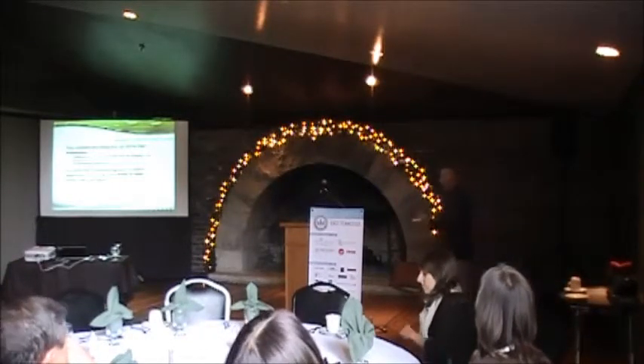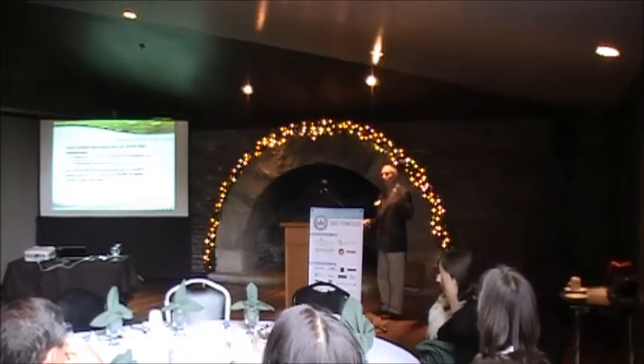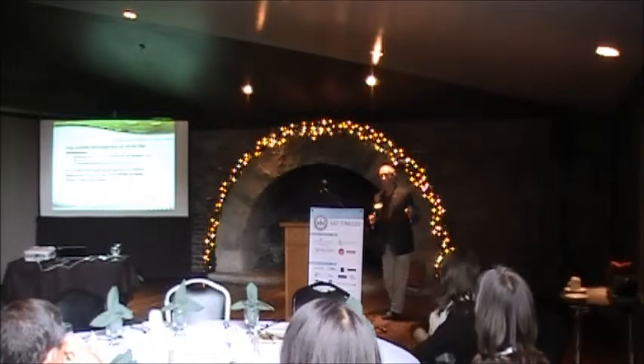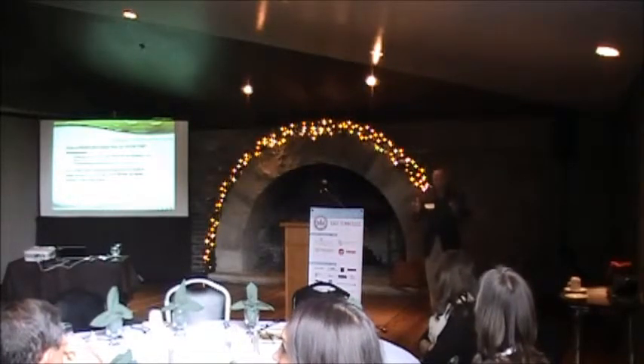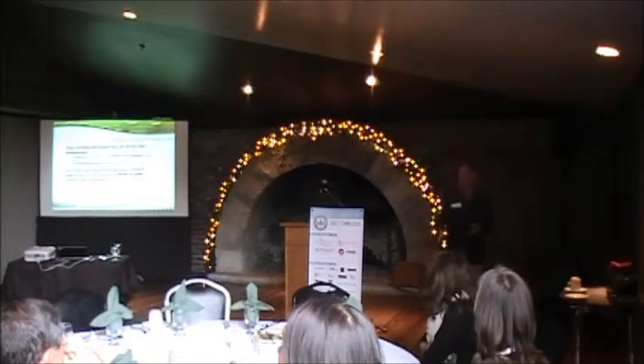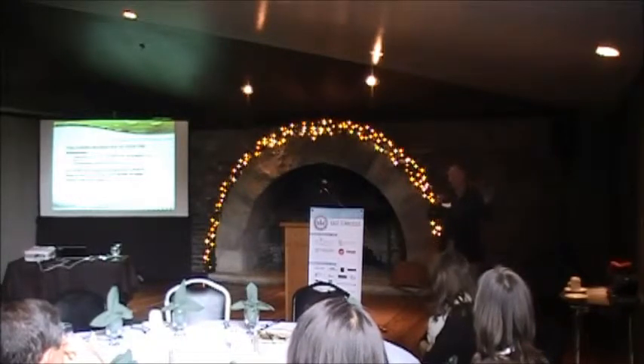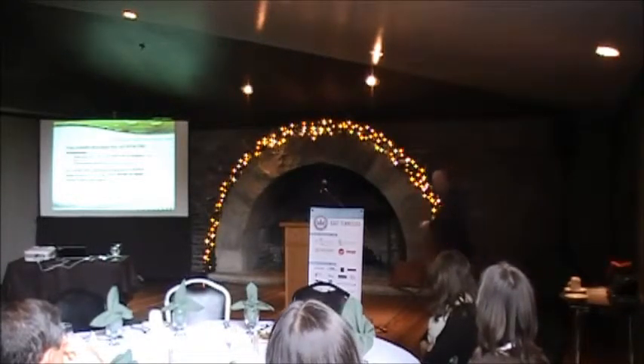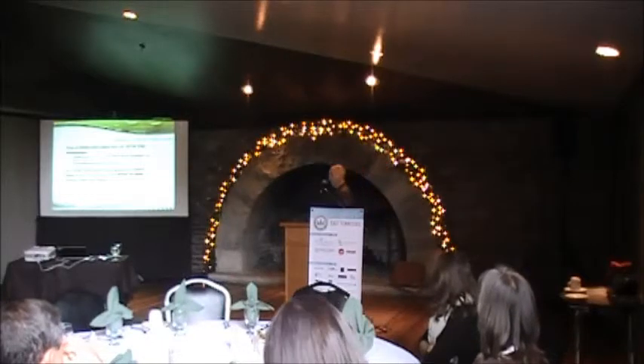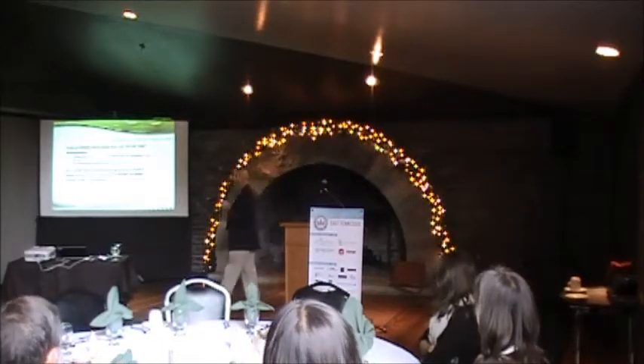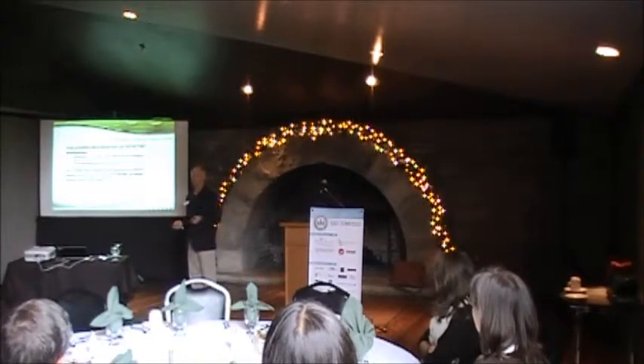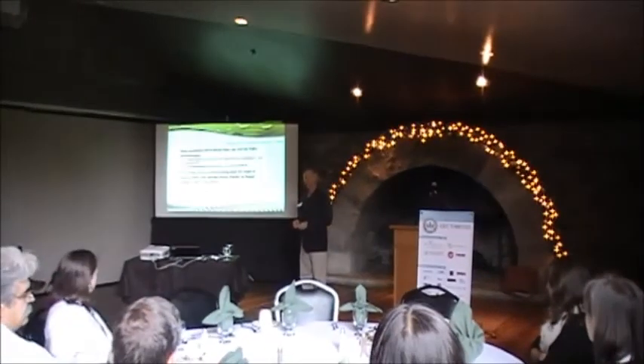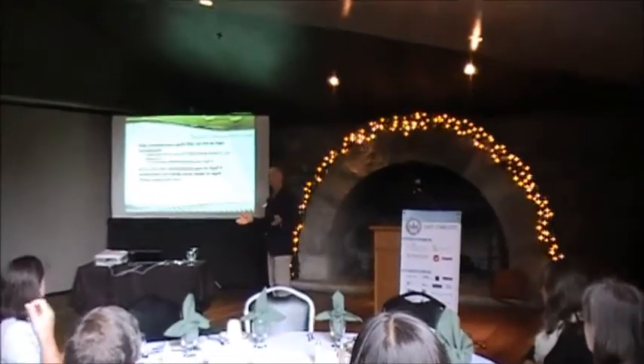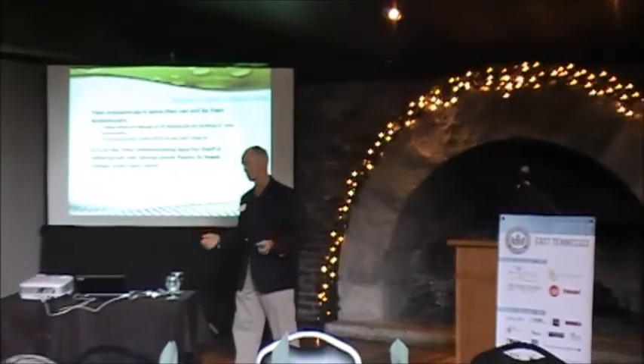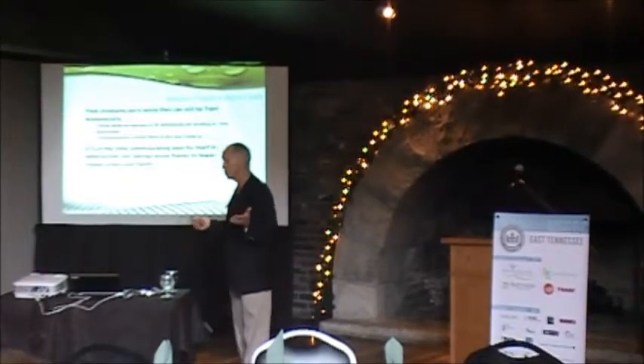So we noted it and commented on it, and everybody said, oh, we've got to fix that, let's move the ductwork over, because it was early in construction and nobody had put the sprinkler piping or lights in yet, so it's no big deal. But what if that had been discovered after 100 of these had been put in, and the sprinkler piping and lighting were already in, and now you've got to move a bunch of stuff to get it out of the way? Then there'd be a lot of gnashing of teeth, pointing of fingers, claims, and so forth. It's just a good example. I can give you many more of issues that were avoided through commissioning.